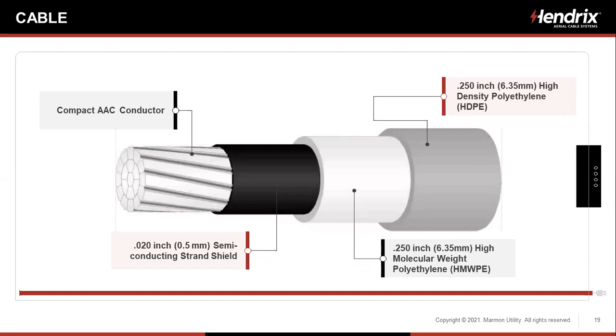The outer layer is where we put a lot of the tricks. That's high density polyethylene, and we're sourcing the highest high density polyethylene that we can source in order to give us a very high abrasion resistance, because there is some anticipation that this will be in contact with a tree at some point. We don't want that jacket to abrade and cause us issues there. It's where we put our UV inhibitor, and that UV inhibitor is a chemical UV inhibitor. It is not fugitive. It's not carbon black. It's a chemical UV inhibitor, and it puts an umbrella on the molecular chains, protecting them from UV radiation. It's where we put our track resistant additive, and it's also where we put our color. So that's what we've got there for the cable. And if you compare that to a 15, 25, or 35 kV system, you would see the same 3-layer system of insulation, only a difference in thickness.